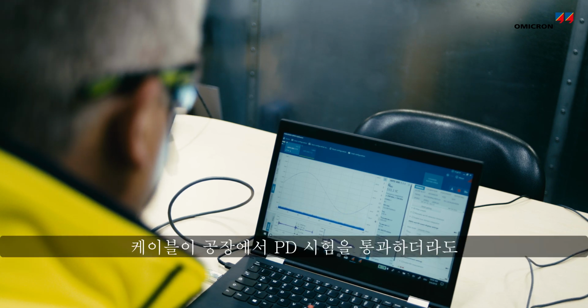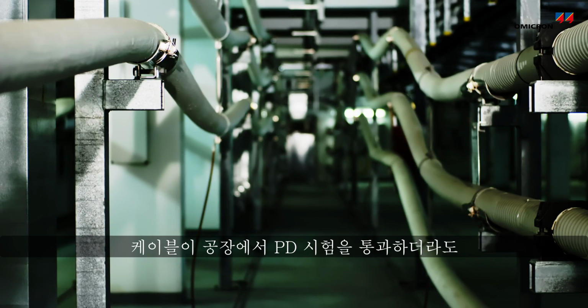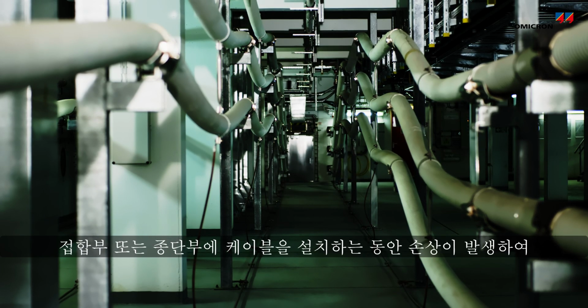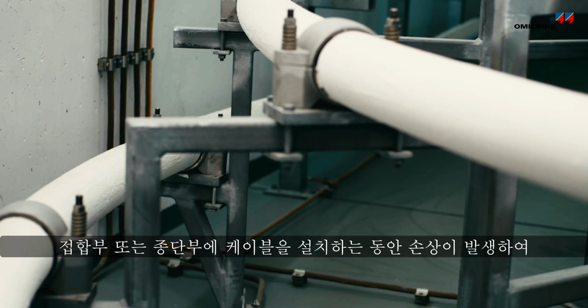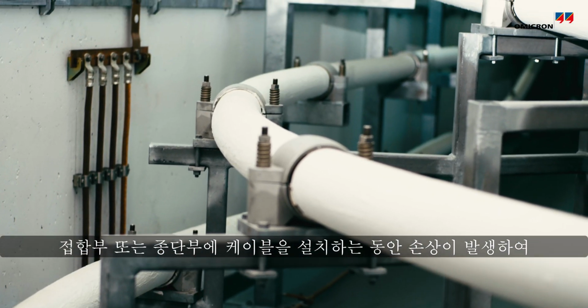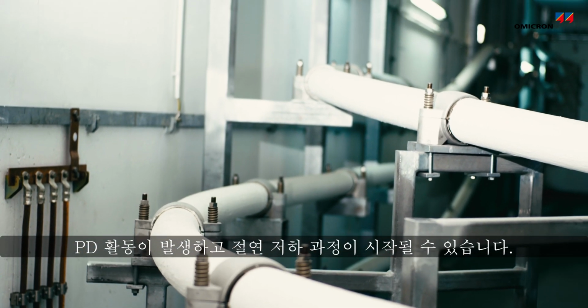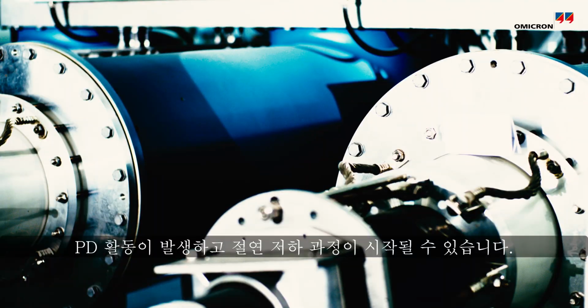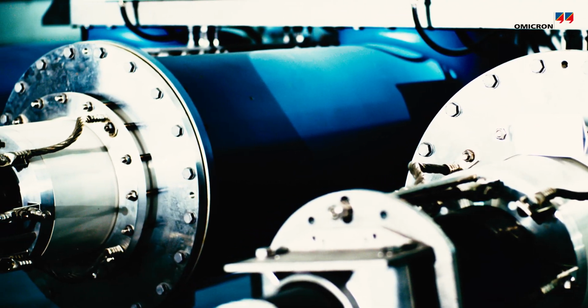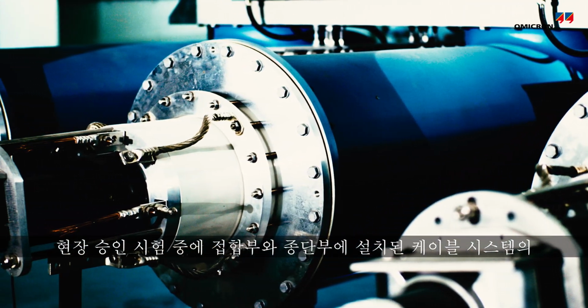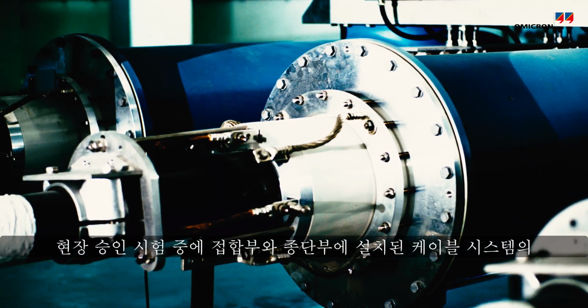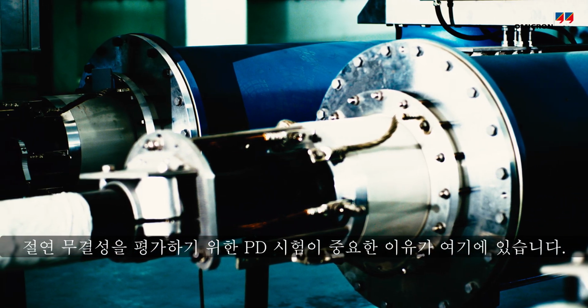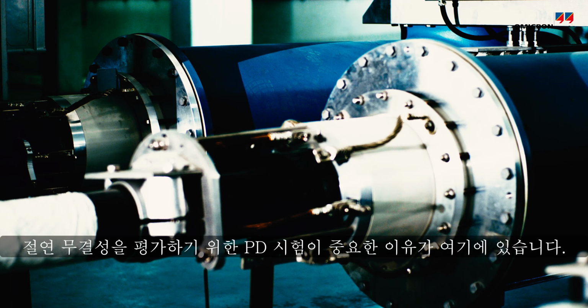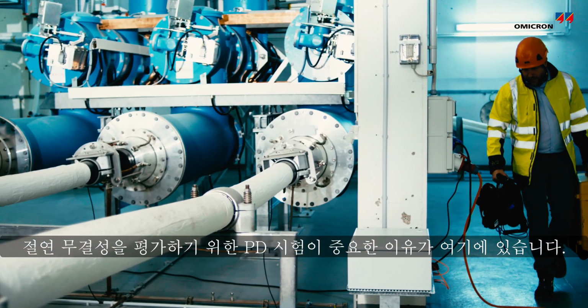Even when the cable passes the PD test at the factory, damage may occur during cable installation at the joints or terminations, which can produce PD activity and initiate the insulation deterioration process. That is why PD testing is also important during site acceptance testing to assess the insulation integrity of installed cable systems at their joints and terminations.